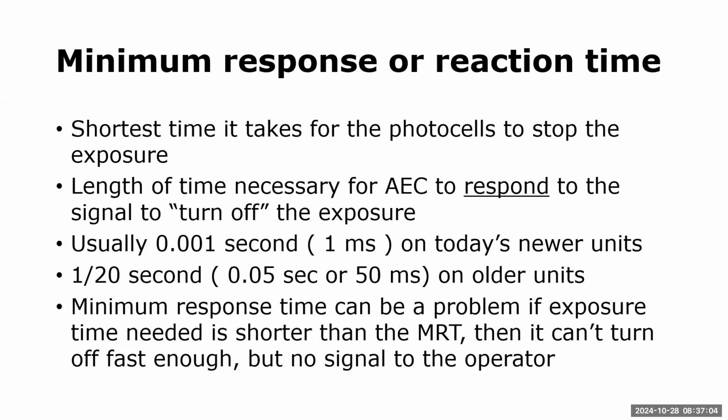So that's where it becomes a problem. So that's why the newer machines have an MRT of about 1 millisecond, because pretty much that's going to cover everybody. That's a pretty quick response time. Okay. Any questions about this? For some reason, this concept a lot of times is not real clear to students. So I want to make sure that everybody understands it and that there's two names for it, because y'all know how I like to put those kind of questions on the test, right? So it can be known as either minimum response or minimum reaction time.